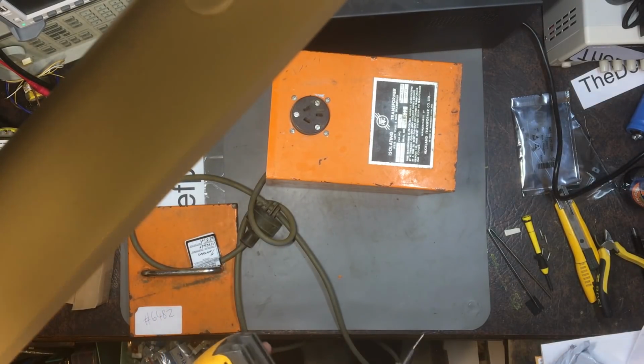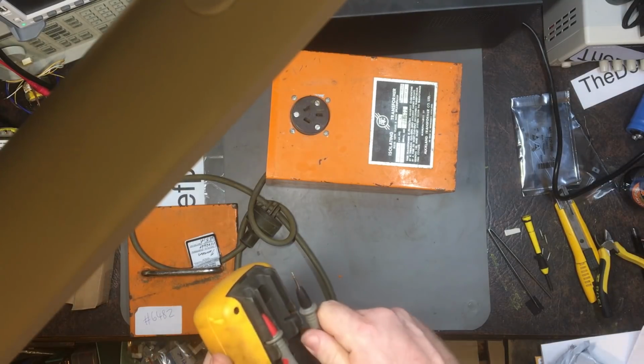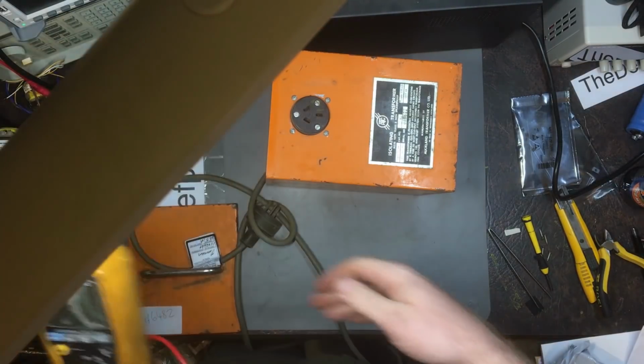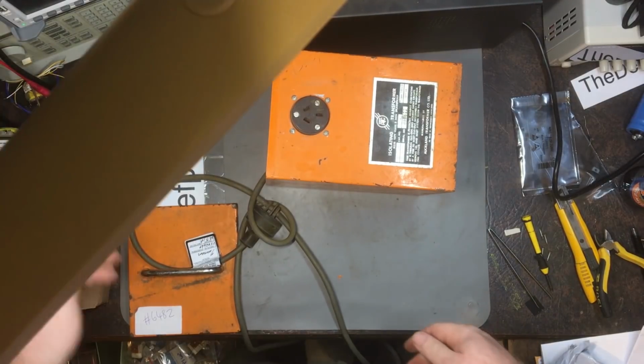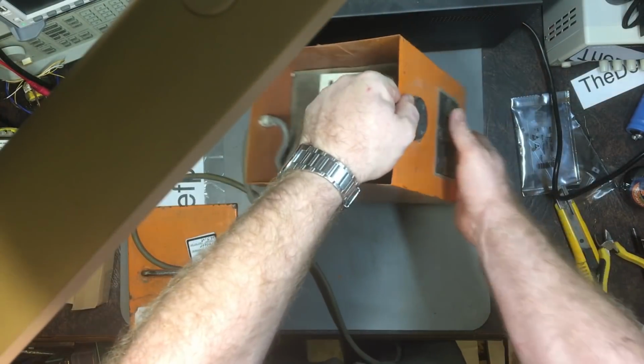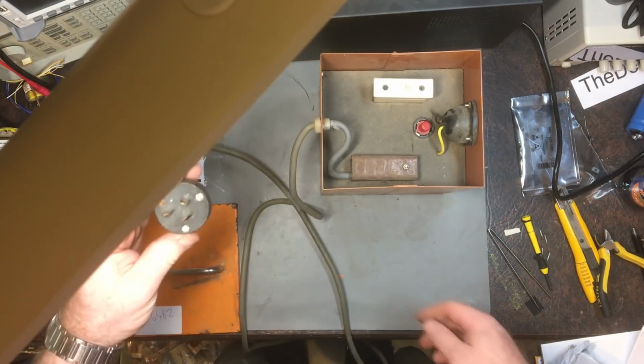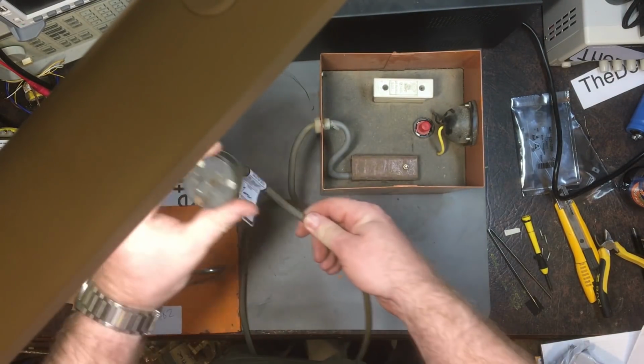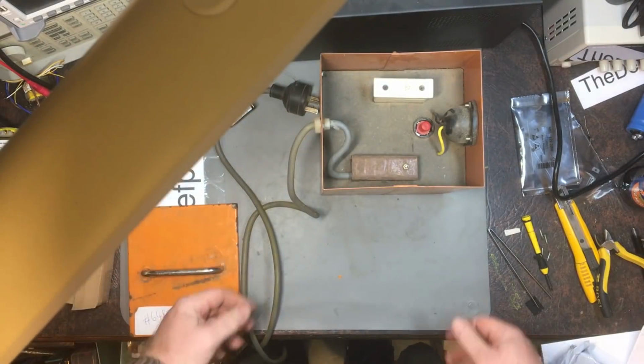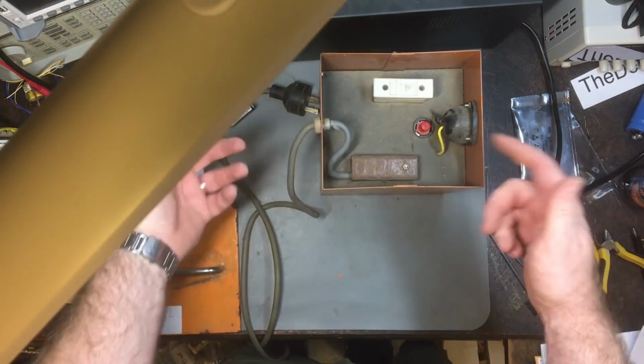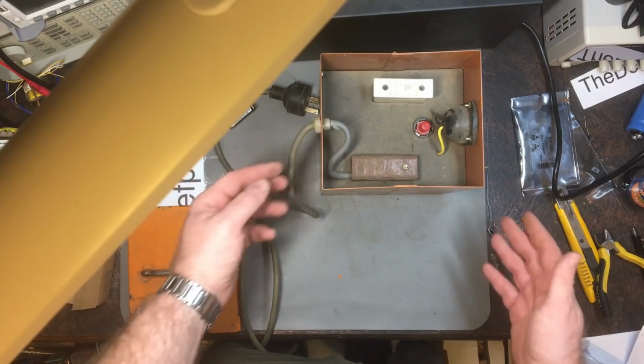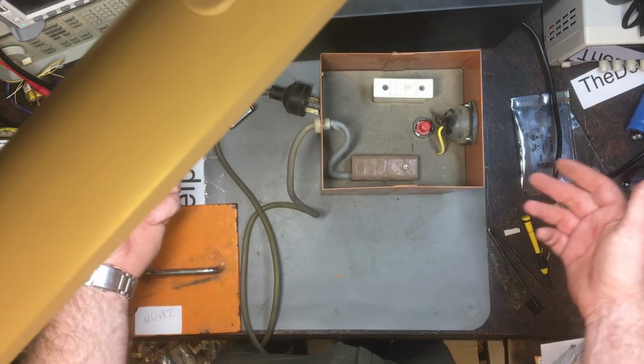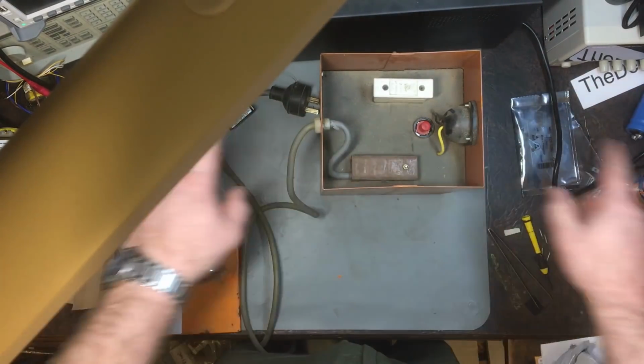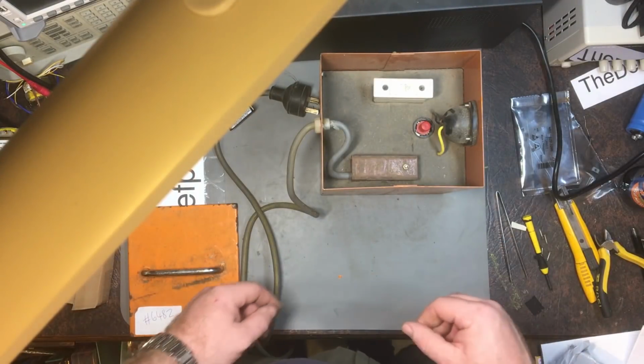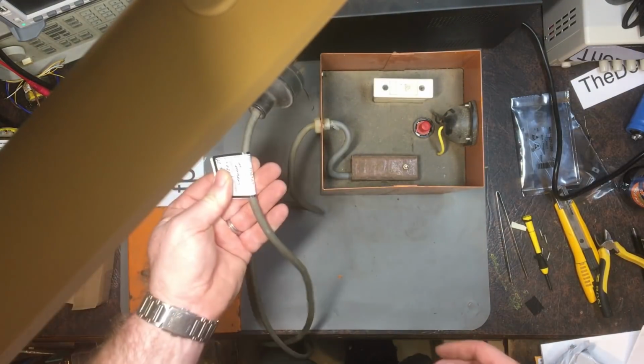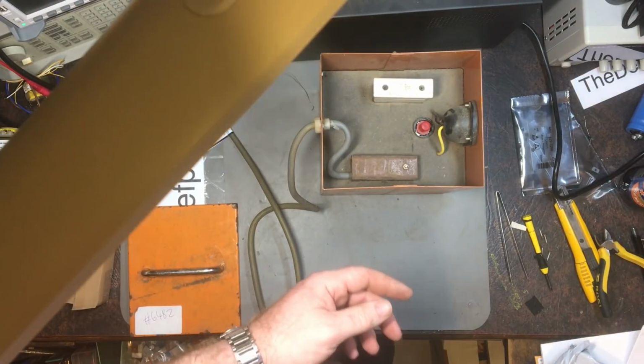I think I might get out my insulation resistance tester from my drawer - it has no batteries in it because I rarely use it. But I might get that out and check the insulation breakdown, just to make sure there's isolation within the transformer from side to side. I can't do that with that other meter since there's no voltage involved, so I need to do a high voltage test from one side to the other to make sure there's no direct pass through, which is probably something the person who did this tag didn't even consider doing.